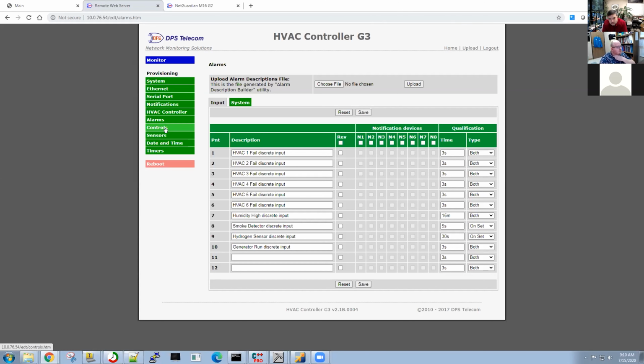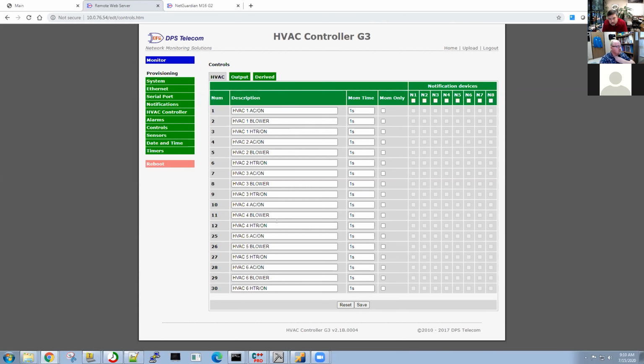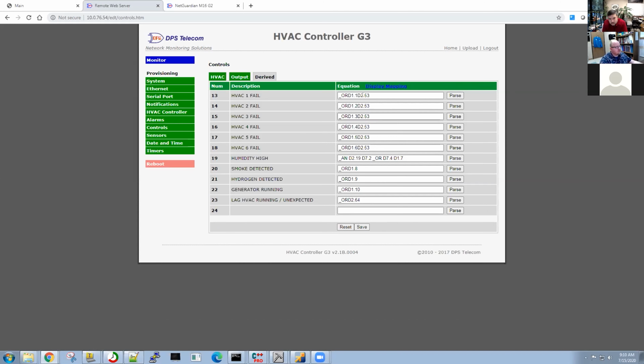That's on alarms - we have controls as well. We can see all these controls have their auto descriptions populated, and some of them are going to have some sort of derived alarm logic. All of this was auto populated in here, but it basically boils down to a Boolean logic evaluation of different alarm points on the unit to determine when these controls should be triggered on or off.